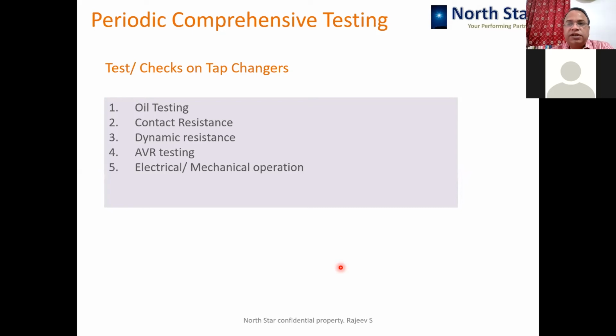Okay, you can do the DGA also on the OLTC oil, but normally DGA doesn't give you much result because in OLTC the oil gets deteriorated only because of the arcing or creation of the carbon. So there is nothing else causing the gases to be generated. So normally you find acetylene in the OLTC is high. So it doesn't help much when you conduct the DGA on the OLTC oil.